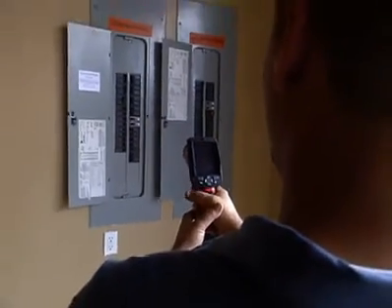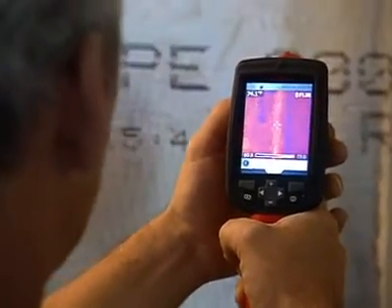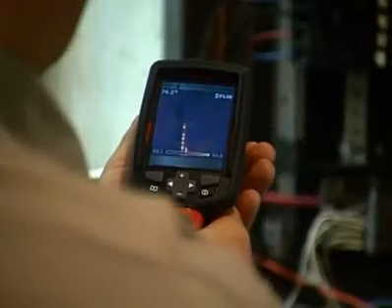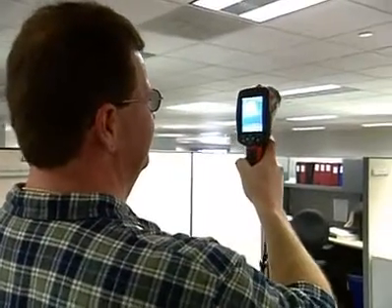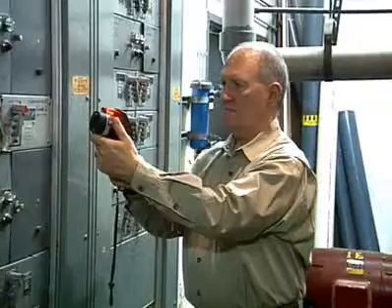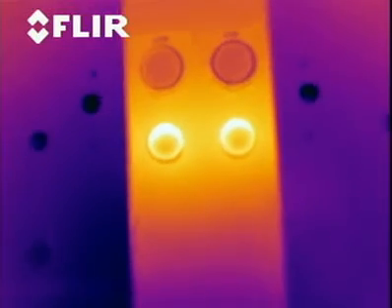With the camera, it enables us to go out and do preventive maintenance. It's a service that in most facilities you never get to do because of the expense — it's quite expensive to go out and hire that service. Depending upon how big your building is or how many buildings you have, do the math. The FLIR camera is affordable, and having it in-house, you wouldn't have to call in someone to do an annual inspection. If you had your own camera, you could see things before it gets to the point of a vibration or overheating, and you'll know if your system is running correctly or needs to be addressed at a future time. You can schedule the repairs rather than have an emergency repair.